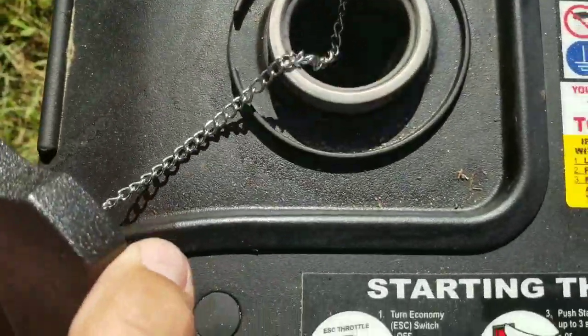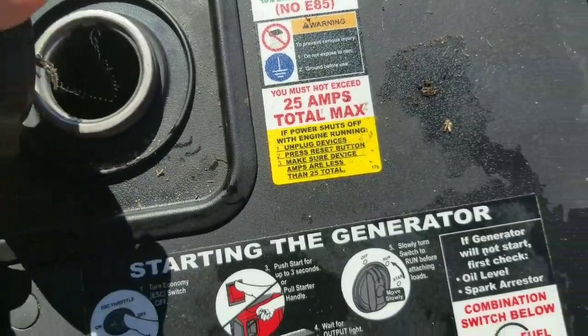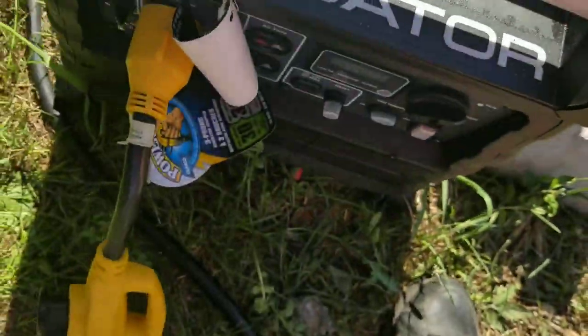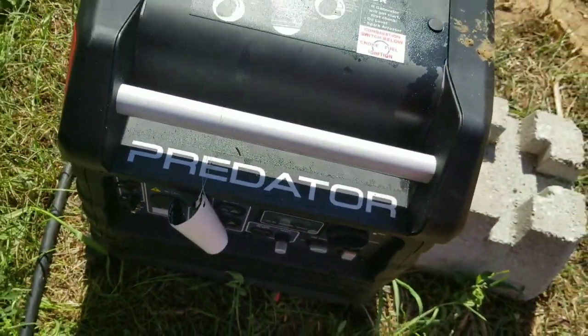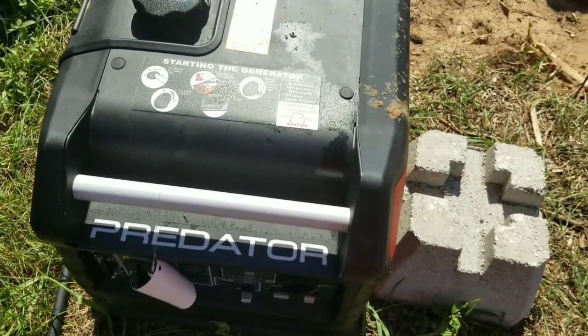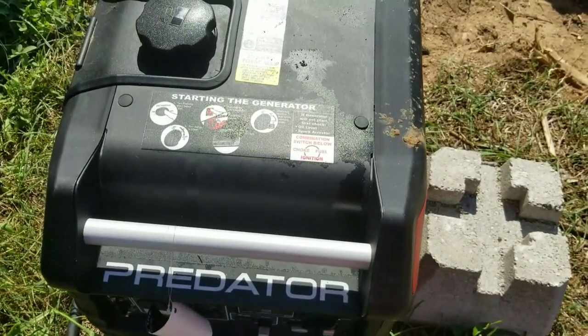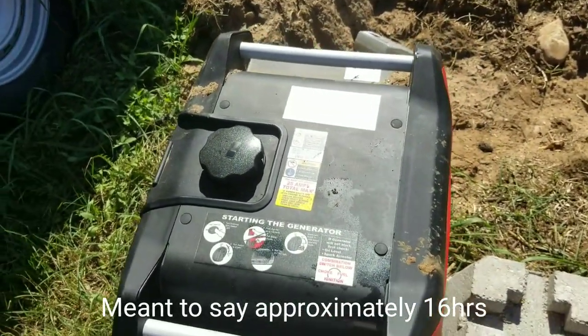Let's see if you can see down in there. I can't even see down there but it's empty, and before I can read the hour meter I have to get fuel in there and get it fired up. But it roughly ran 14 hours on between a quarter and a half load — that's what it had for 14 hours and it ran through that 2.6-gallon tank.